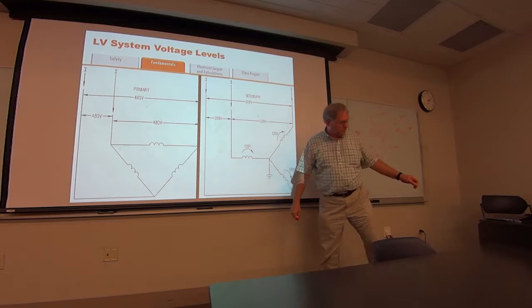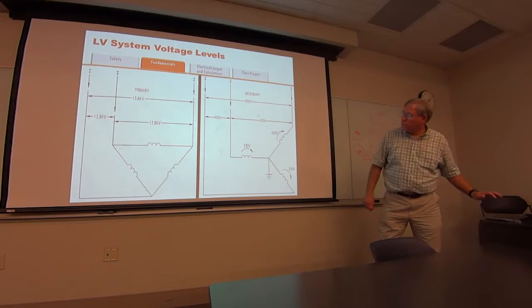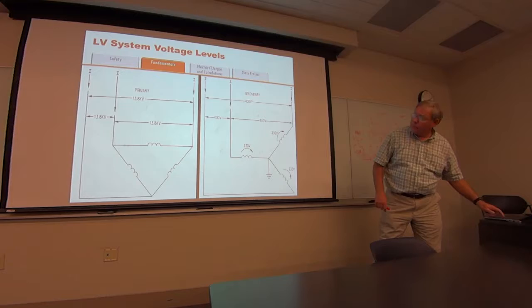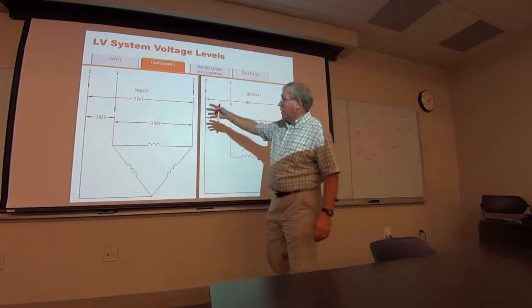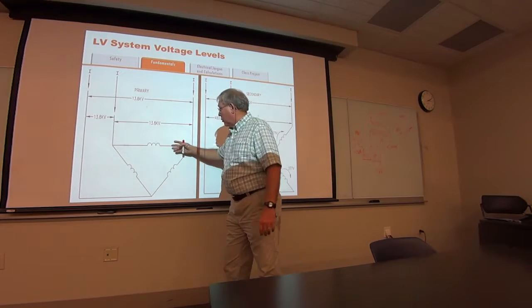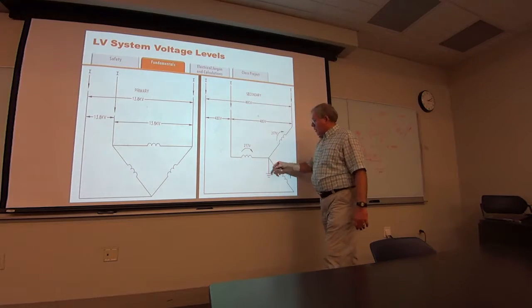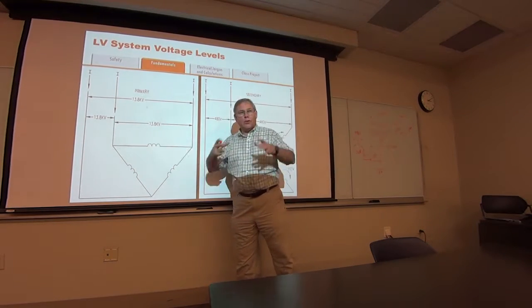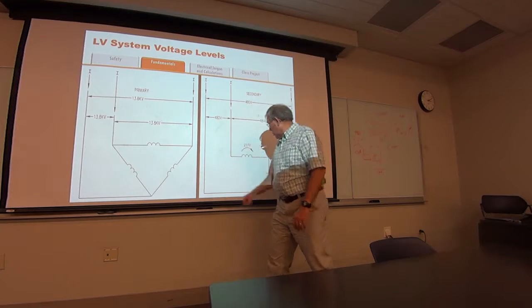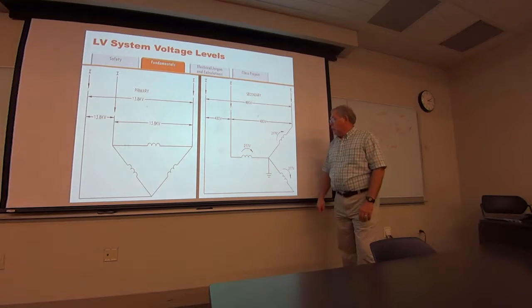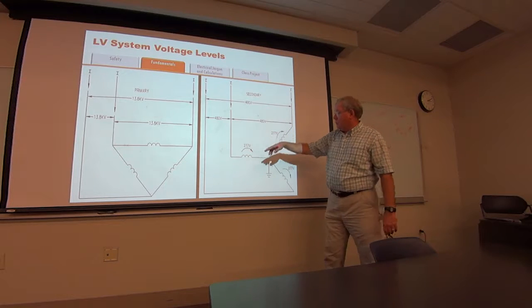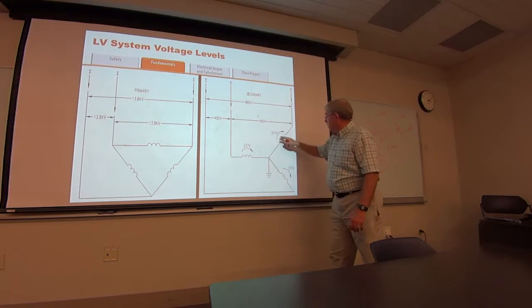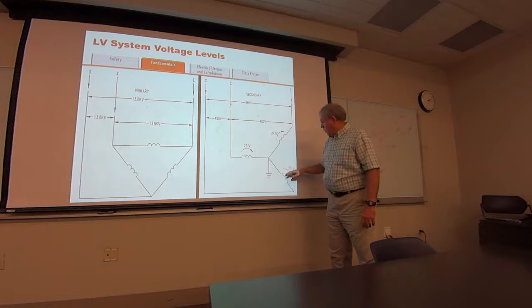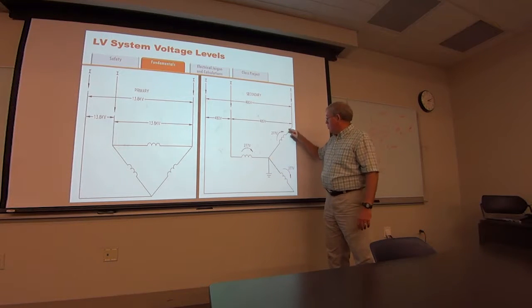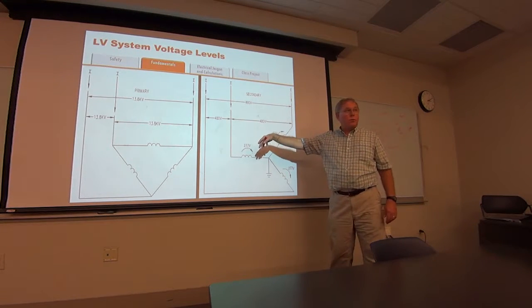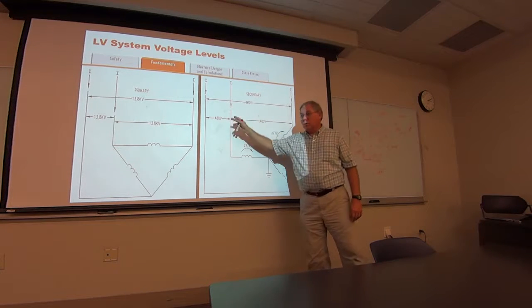Typically in a building, you'll bring it in at 13.8. You go to a delta-Y transformer, and this coil and this coil are on the same core. Then that one steps down from 13.8 to 277. And the voltage you see across the coils is 277, but when you put them in this arrangement, because of the phase angles, and we'll do that in a minute, you get 480 volts across them.